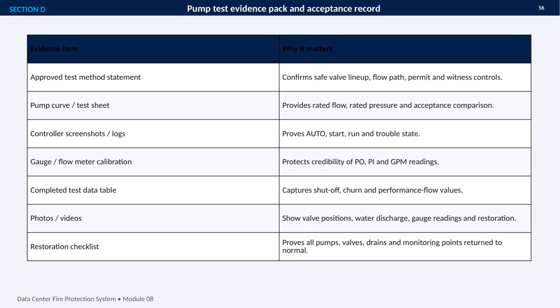The completed data table then captures the important test points, including shutoff, churn, and performance flow values. Photos or videos provide visual confirmation of valve positions, discharge, readings, and restoration. Finally, the restoration checklist confirms that the system was returned to normal, with pumps, valves, drains, and monitoring points all checked. A strong acceptance record connects every result to objective evidence.